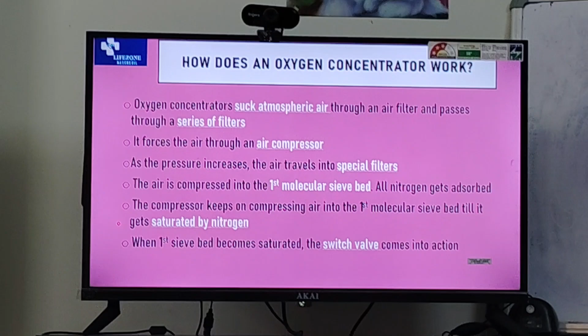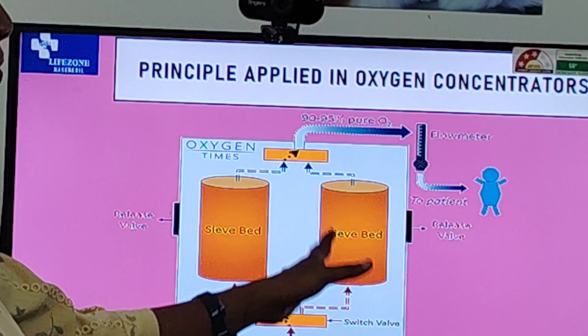You can see a molecular sieve bed, and the air passes through the sieve bed, and as the nitrogen particles are larger than the oxygen molecules, they get trapped in the sieve beds, and when it gets saturated with nitrogen, there will be valves which will switch and it will move to the second bed, and the compression starts working in the second sieve bed. When it gets saturated, the air with pure oxygen moves to a collection tank, and from the tank it passes to the patient, and there will be a flow meter which controls the flow of oxygen to the patient. So this is about the working of the oxygen concentrator.